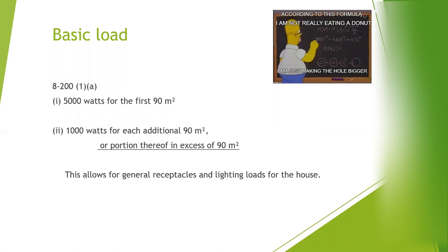For our basic load, looking at Rule 8-200, it says the load for a service or feeder supplying a single dwelling shall be based on the greater of items A or B. Focusing on item A, item i: a basic load of 5,000 watts for the first 90 meters squared, then 1,000 watts for each additional 90 meters squared or portion in excess of 90 meters squared. This accommodates the general receptacles and lighting loads in the house.